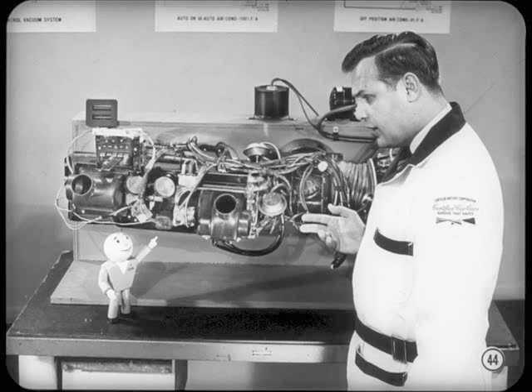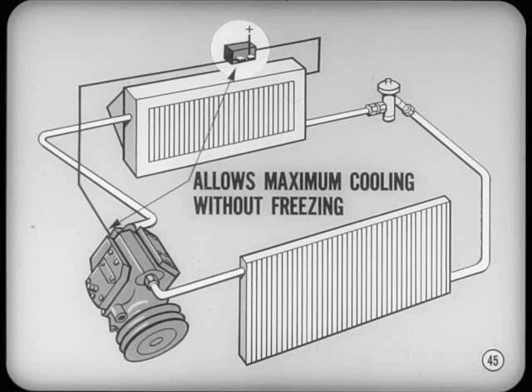The evaporator anti-frost control is also an independent circuit. You lost me. What do you mean by anti-frost control? The evaporator anti-frost control system allows the evaporator to provide maximum cooling without danger of freezing moisture that is condensed out on the evaporator fins and tubes. But how does it work?